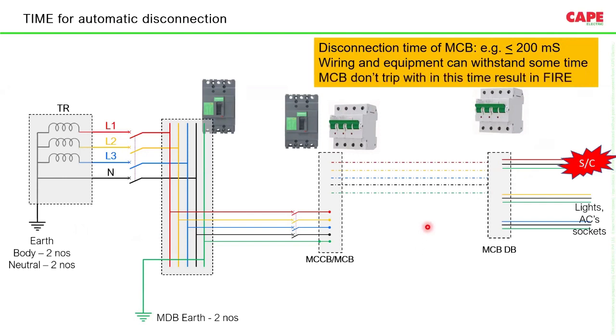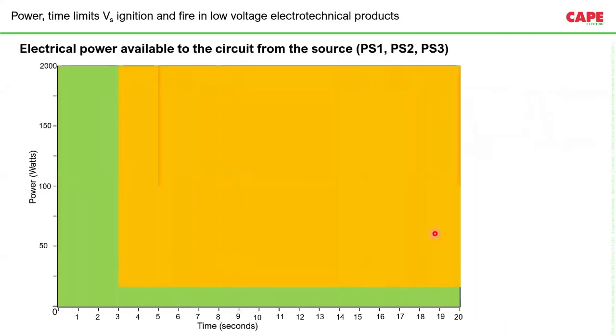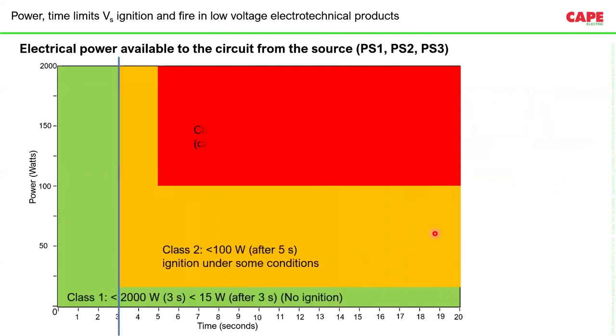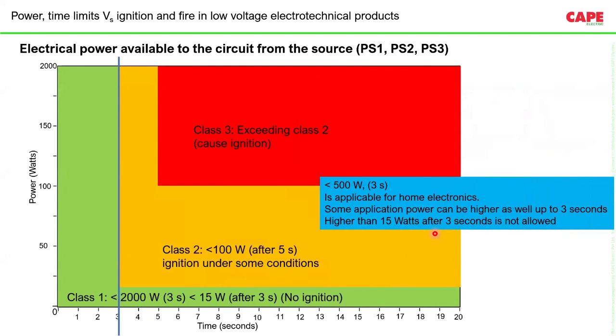You must understand that wiring and equipment can withstand a higher current only for a short time. So basically, the disconnection may not happen. Now, with respect to fire, there are a few concepts included in the design standards. One of the concepts, in the figure which you are seeing, is the green color, power in watts. It is nothing but the power dissipated due to a fault. Whatever the maximum power, let us say 4,000 watts or 2,000 watts, if the fault is cleared within 3 seconds, the chance of ignition of fire is quite less.